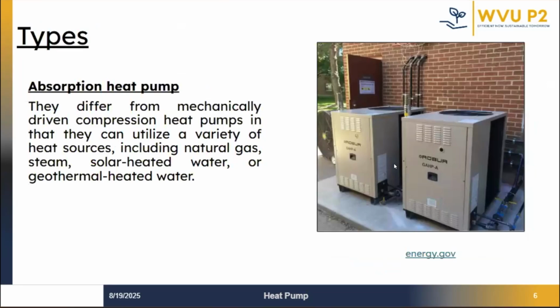The third type is the absorption heat pump, which operates quite differently from the other two. Unlike traditional heat pumps that use electrical compressors, absorption systems rely on a thermal energy source, such as natural gas, steam, solar heated water, or geothermal heated water to drive the heat transfer cycle. Instead of using mechanical compression, they use a chemical absorption process, typically involving a refrigerant-absorbent pair like ammonia-water or lithium bromide-water. Absorption heat pumps are ideal for industrial or large commercial applications, especially where waste heat or non-electric energy sources are available. They are quite reliable and can be used in areas where electricity costs are high or grid infrastructure is limited. While less common, they play a valuable role in district energy systems, combined heat and power plants, and facilities with solar thermal integration.